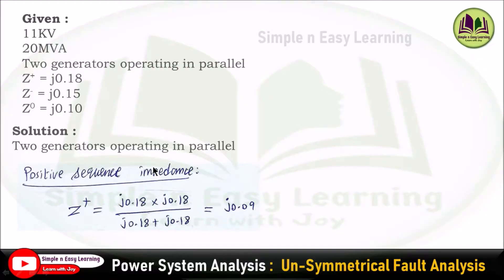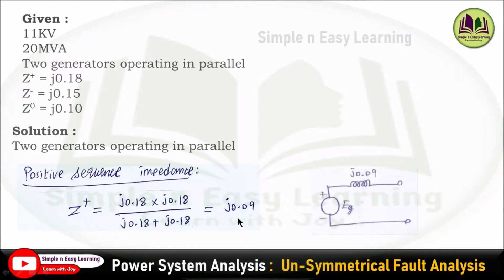First, positive sequence impedance. For parallel operation of generators, we do the parallel combination: Z+ = (J0.18 × J0.18) / (J0.18 + J0.18), giving J0.09. This is the positive sequence impedance. The sequence network is represented with induced EMF and impedance Z+, where EG and Z+ equals J0.09.